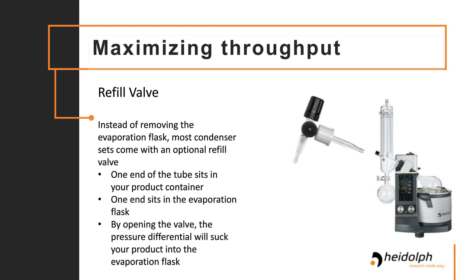A refill valve is another way to really maximize the throughput of your rotary evaporator. Every time you have to remove your evaporation flask, that's time that you're not evaporating. Well, what the refill valve will allow you to do is you pop it into a carboy or a container with your product, you open the valve, and the pressure differential between the inside of the rotary evaporator and your product outside will suck it up and into your evaporating flask without you having to remove it. So that'll allow you to evaporate two or three times before having to grab your evaporation flask and actually dump it out, really increasing your evaporation time and meaning that you don't have to fiddle with it as much.